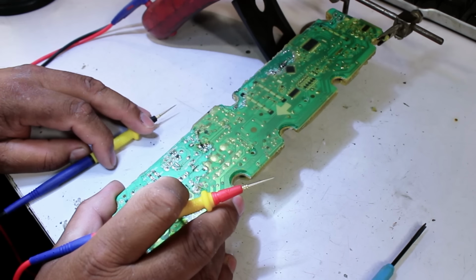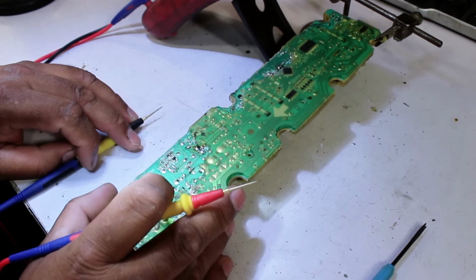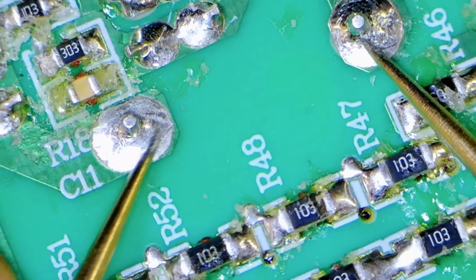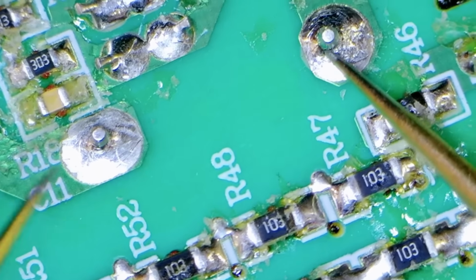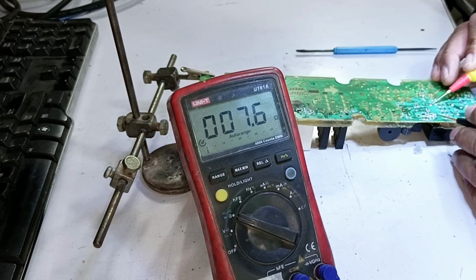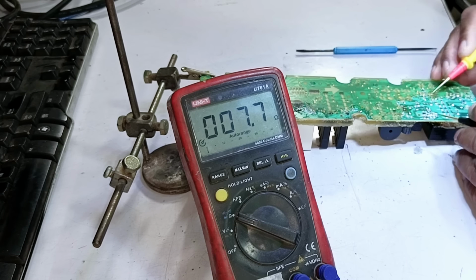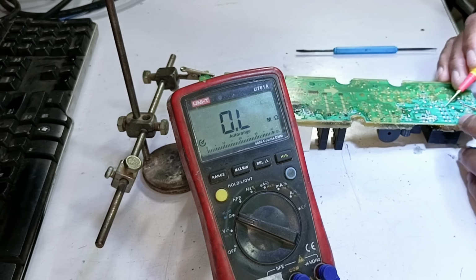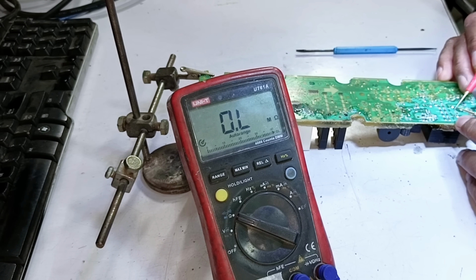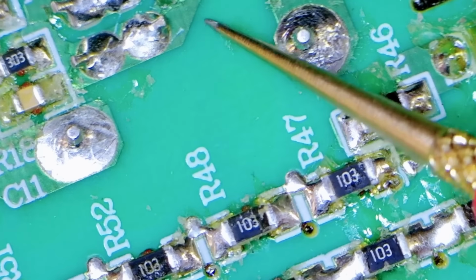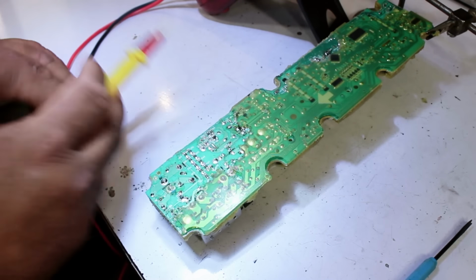Since the high side is completely okay, we will also check its low side. These 2 points here are the low side points, so we check them as well in resistance mode. It is showing 7.7 or 7.6 ohms, which is completely okay according to the ratio. Since it has to convert into 12 volts, one side is 2 kilo ohms and the other side is 7.7, which is perfectly fine according to the ratio.